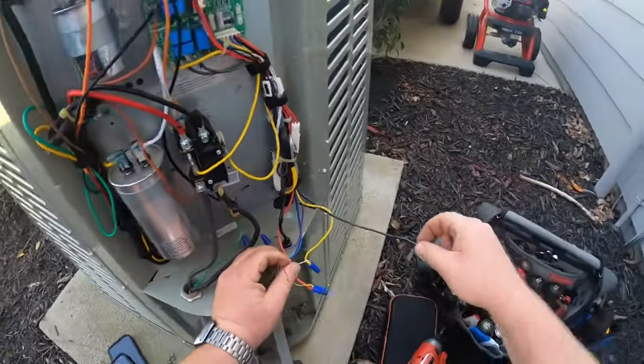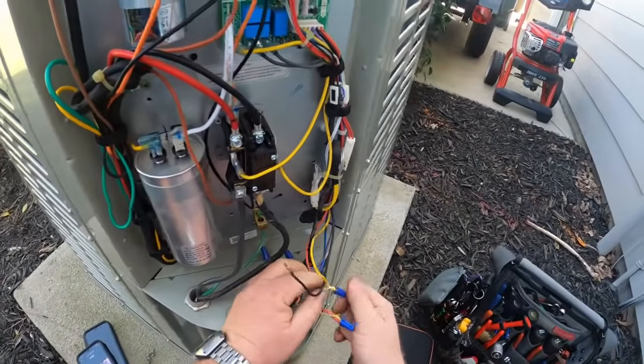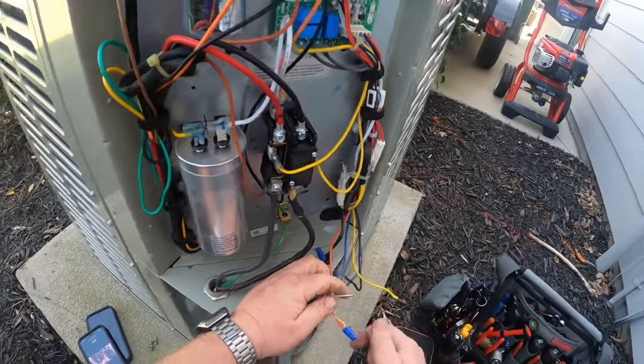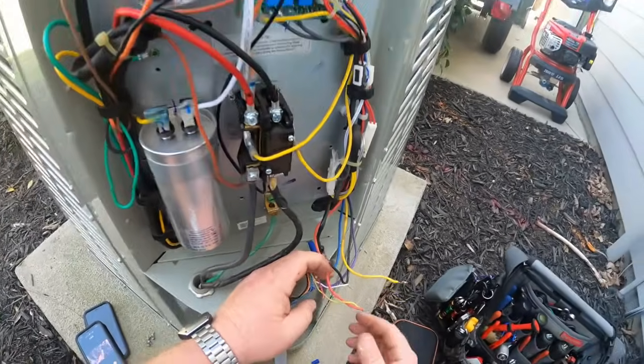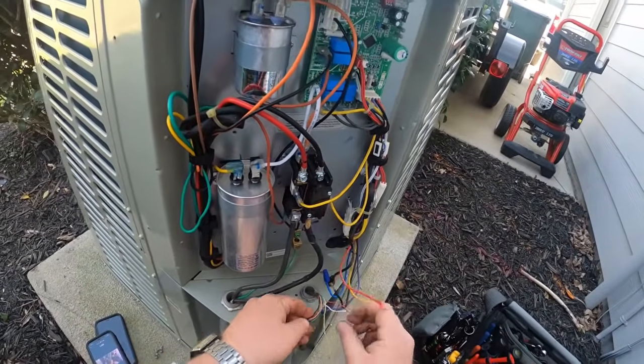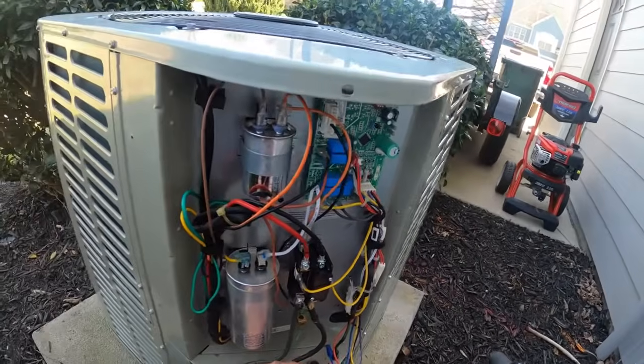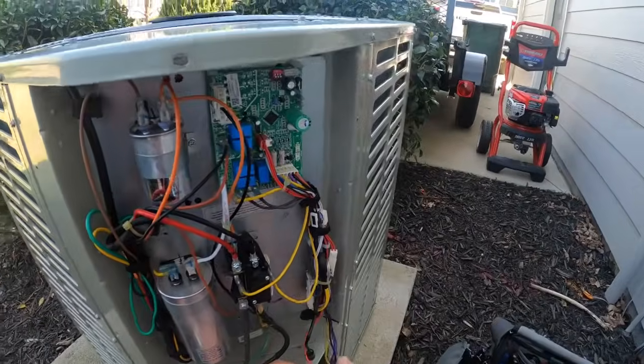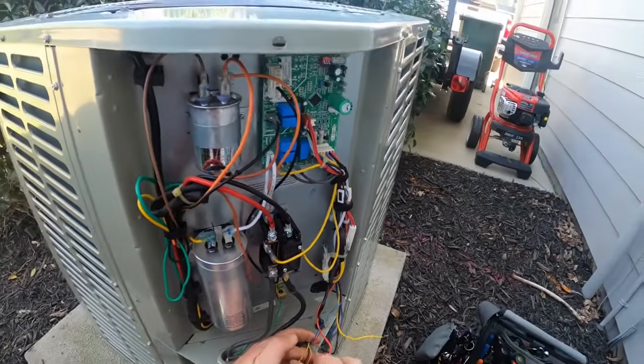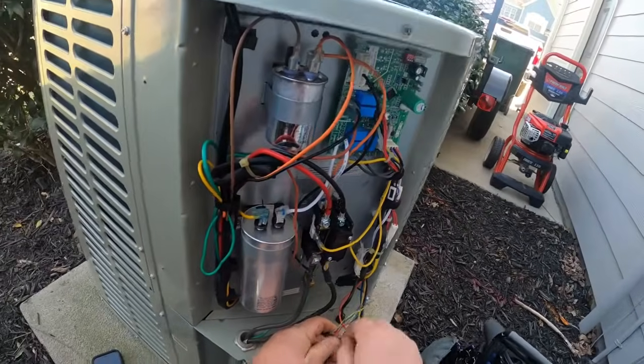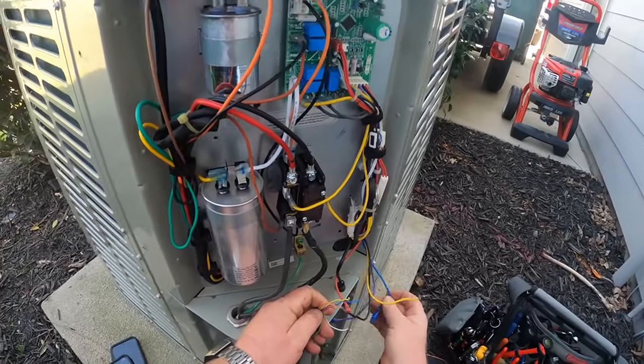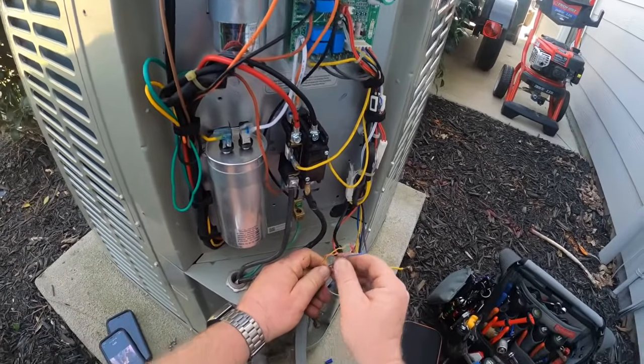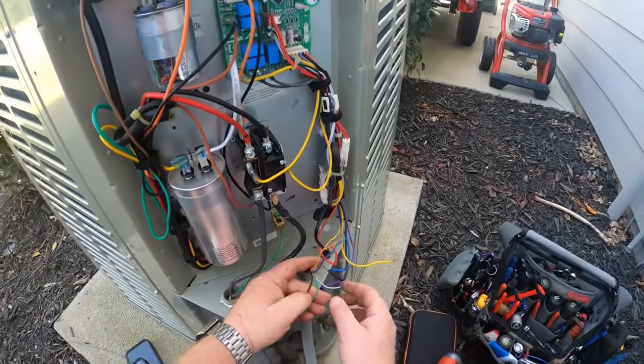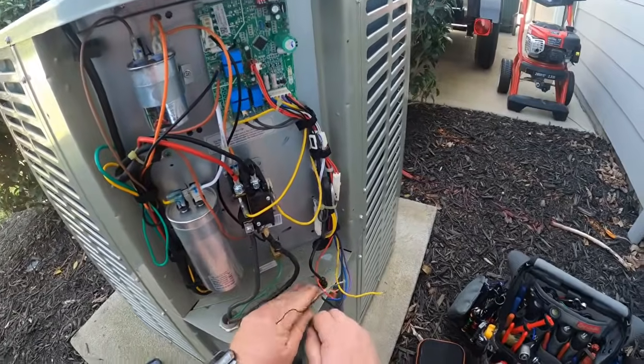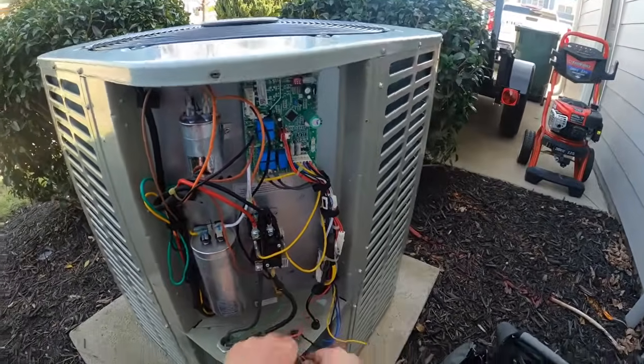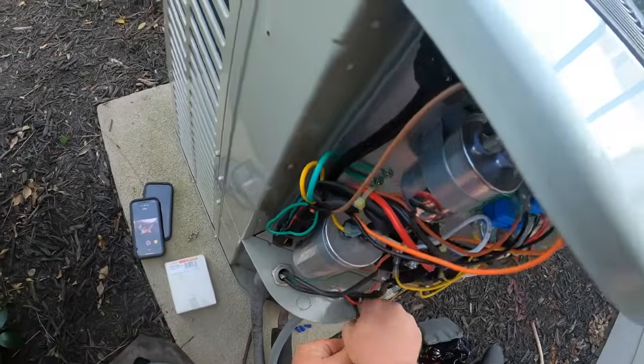You see, he was using white up there for Y and using yellow for red. I've changed all that to pretty much standard, the way I like things to be, which is obviously my R for 24, my blue for common, and I'm going to use my yellow for Y. I'm going to use orange for my reversing valve, but that's going to go to my blue over here for B, to energize in heat. And then I typically will use my black to go back in for my auxiliary heating when it goes into defrost, to go back in there and energize.